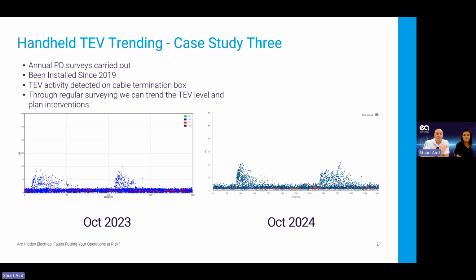And then this next one is a case where we've been trending a transient earth voltage measurement. Transient earth voltage, mentioned earlier, is related to internal partial discharge. So we're expecting an internal void within some insulating material in this area of the switchgear. Each year we go to this particular site and we carry out a partial discharge survey.